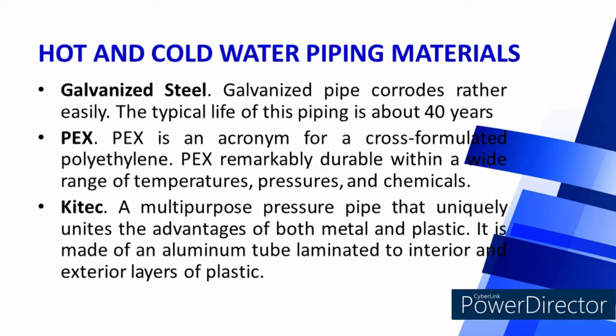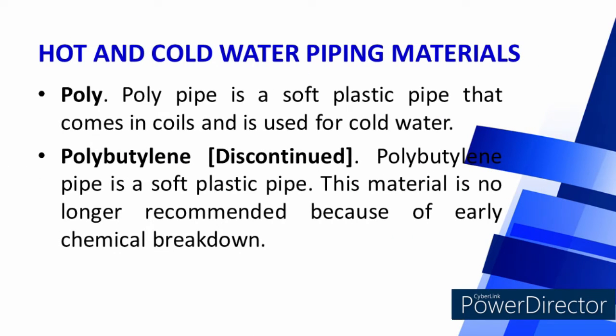Galvanized steel pipe corrodes rather easily, with a typical life of about 40 years. PEX (cross-linked polyethylene) is remarkably durable within a wide range of temperatures, pressures, and chemicals. Kitec is a multipurpose pressure pipe that combines the advantages of both metal and plastic, made of an aluminum tube laminated to interior and exterior layers of plastic. Poly pipe is a soft plastic pipe that comes in coils and is used for cold water. Polybutylene is also a soft plastic pipe, but is no longer recommended because of early chemical breakdown.